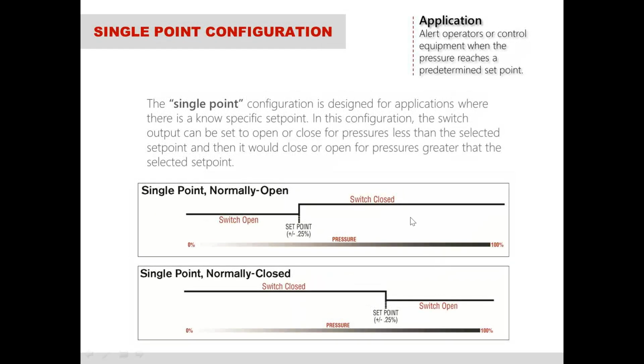We also have the next 2, which are the single point configuration. So the single point is you define one set point. When the pressure is below that set point, the switch is open. When it's above, it's closed. And then vice versa, you can set it where the switch is closed below the set point and then open above the set point.